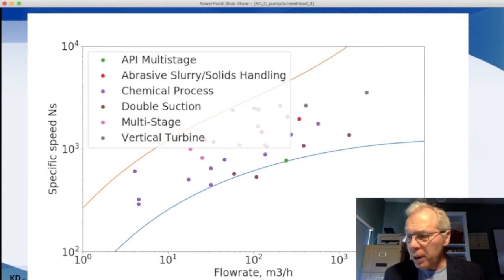As well, that old graph from Worthington predicts pump efficiencies that are often within 2 or 3% of the actual vendor data. And that's pretty good for a graph that's over 50 years old.